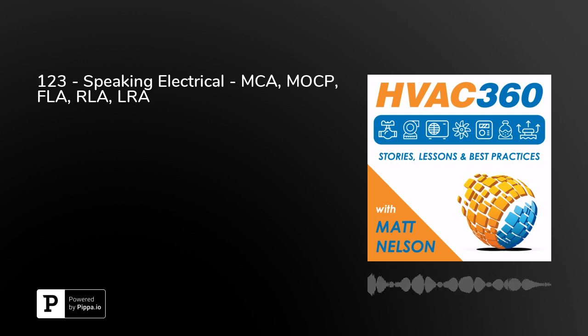You cannot interchange these. The rated load amps is a mathematical calculation. They've been doing that since 1972. And it's critical that you don't confuse it with FLA. Those two things are totally separate. But again, you have all these three-letter acronyms, and you're like, what is the difference? So I'm just trying to help you out, figure out exactly what the difference is for these different abbreviations and acronyms.